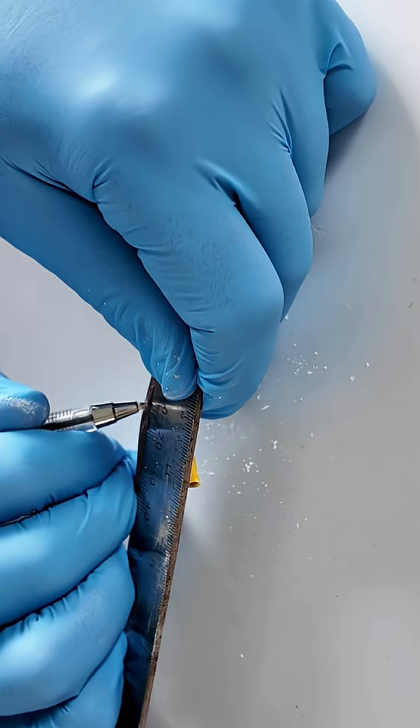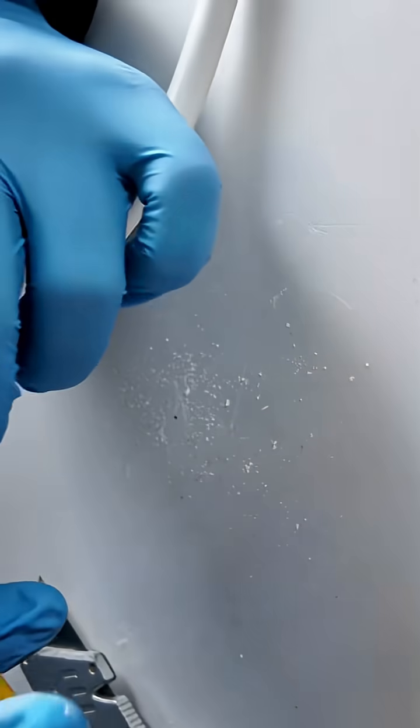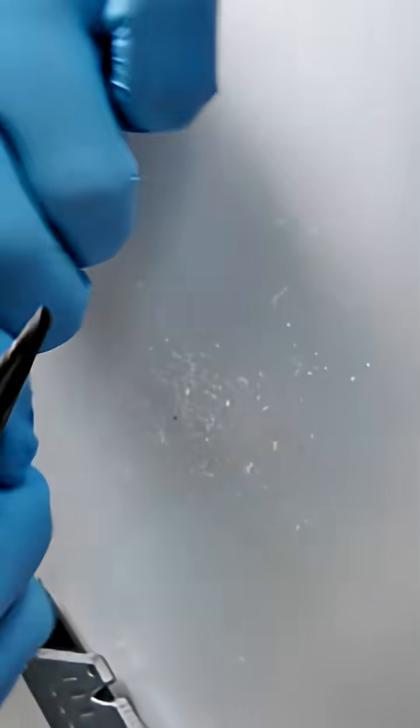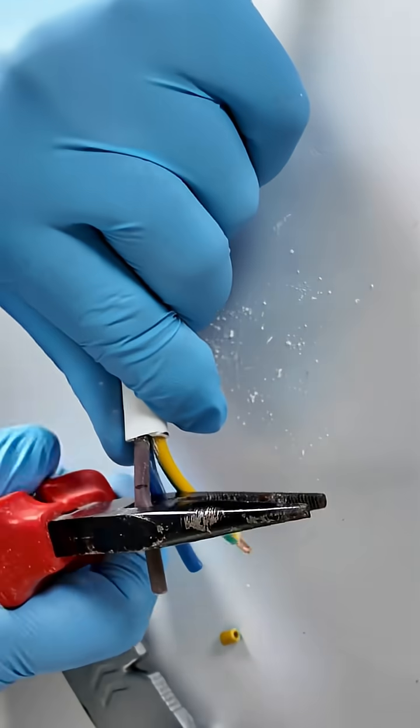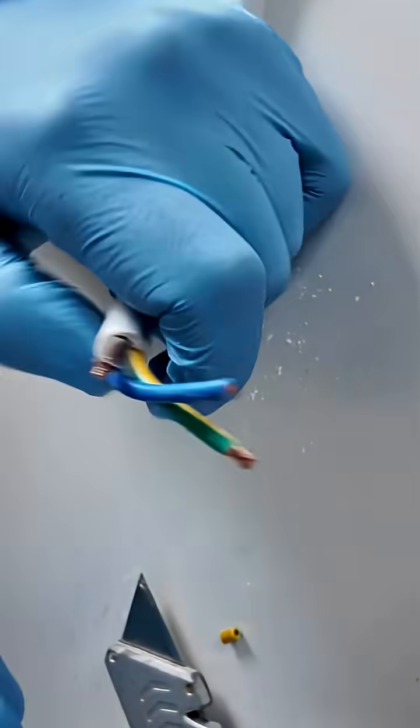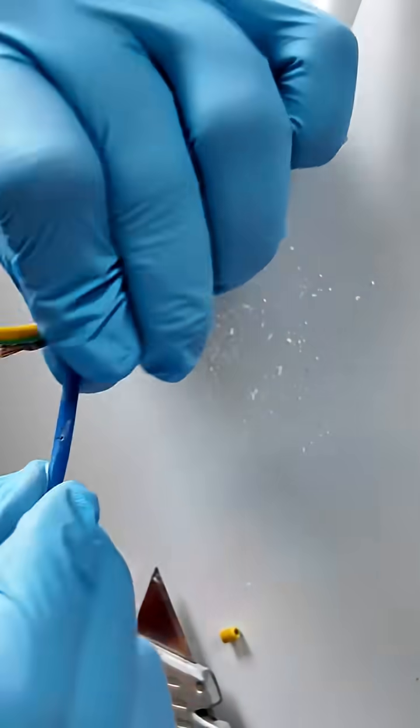Green-yellow earth: leave this wire 32 mm from the outer insulation. Blue neutral: cut to 22 mm. Brown live: 12 mm. Strip about 0.5 cm of insulation from each wire end.